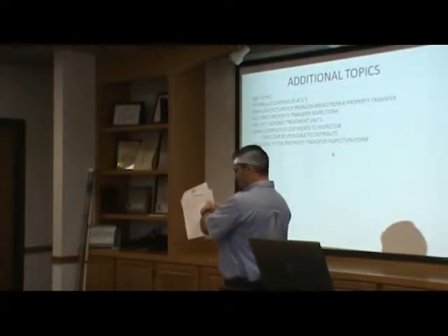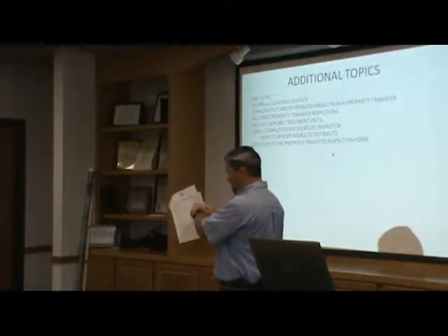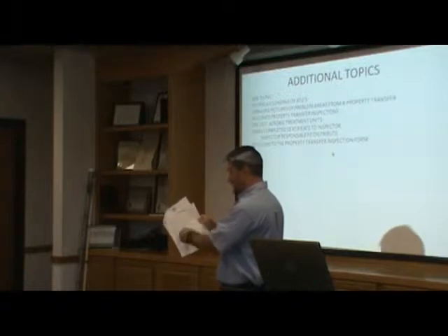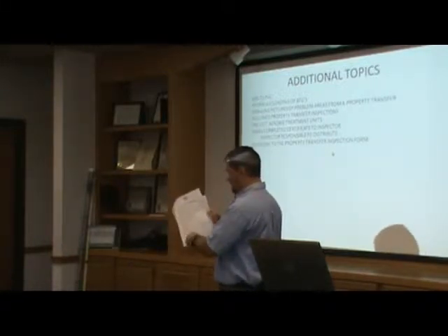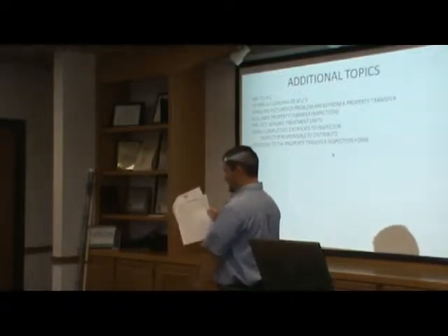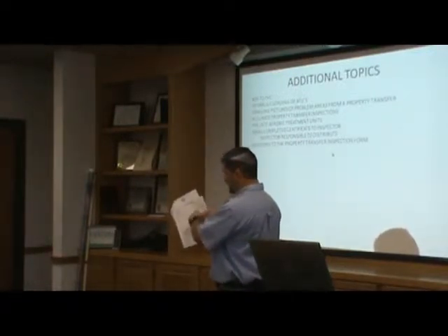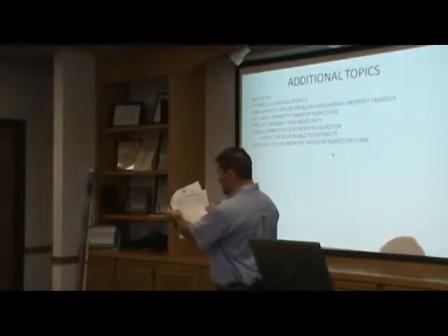At least want to see some type of records, and hopefully you're able to find the leach trench, the depth of it. Is it dry, moist, saturated? So make sure you guys are probing. Probing's not the easiest way, it's the toughest way, but it gives us a good description of what that bed is actually like, versus digging it up. So that all stayed the same.